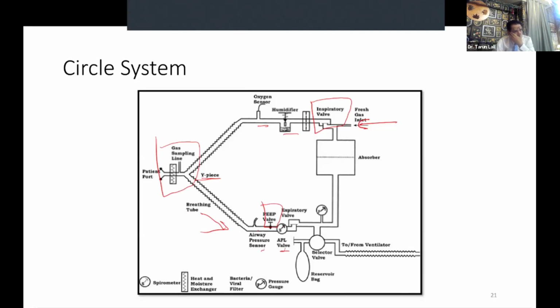But the PEEP valve in this diagram is shown upstream of the expiratory unidirectional valve, though it can be located either before or after the expiratory valve. So we will just cover it.